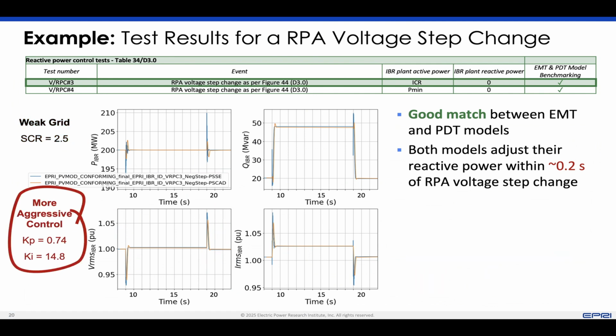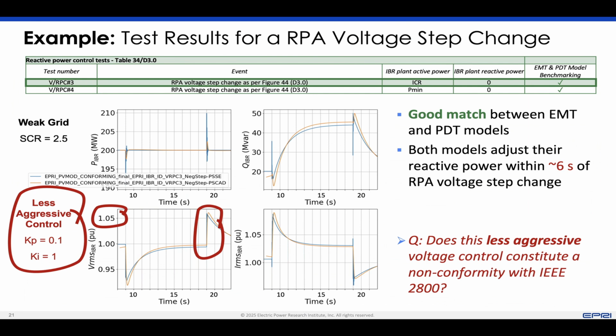Now, when we change the control and make it less aggressive, we actually see that we have a less high voltage. So maybe this is better. Now the reactive power responds within 6 seconds. So the plant's controls have been intentionally slowed down. So those are questions that you can ask yourself. We're not going to give you the answers here. We have a kind of EPRI forum where we're going to look into that in detail.